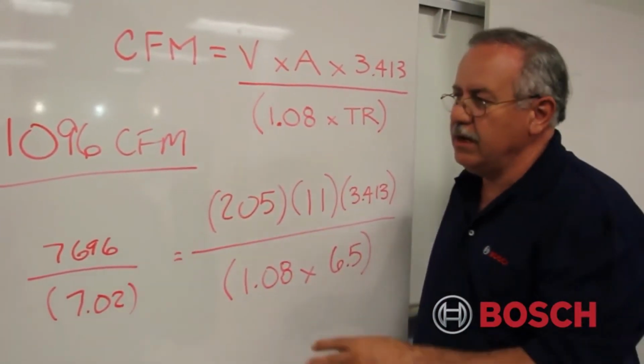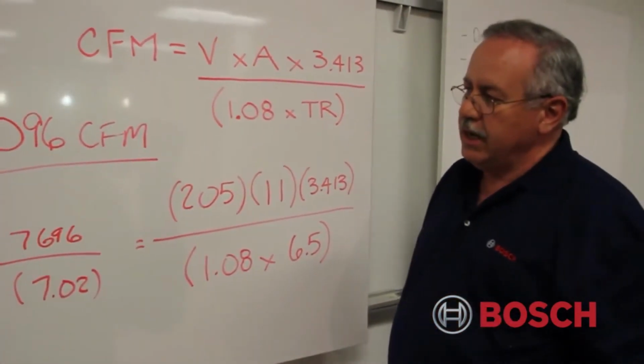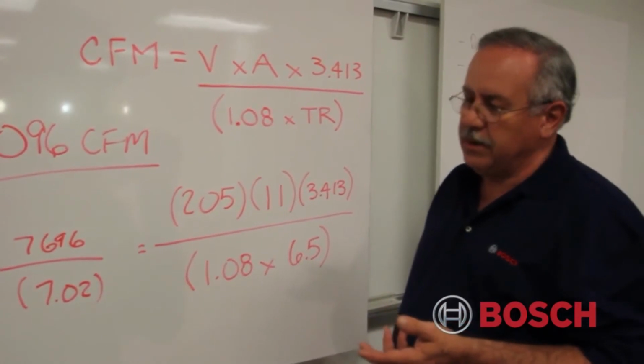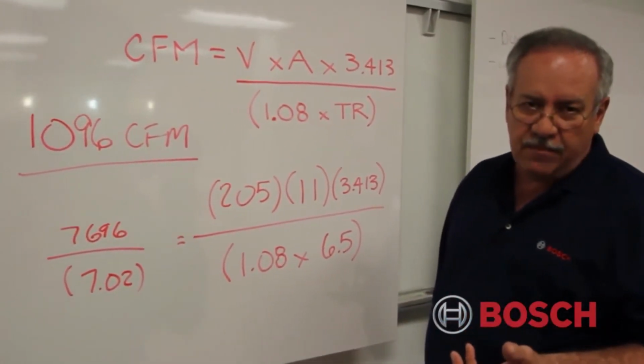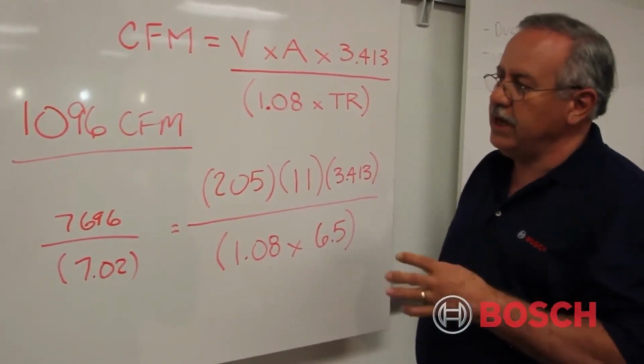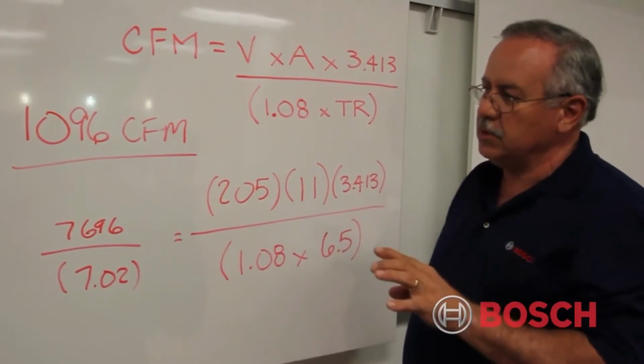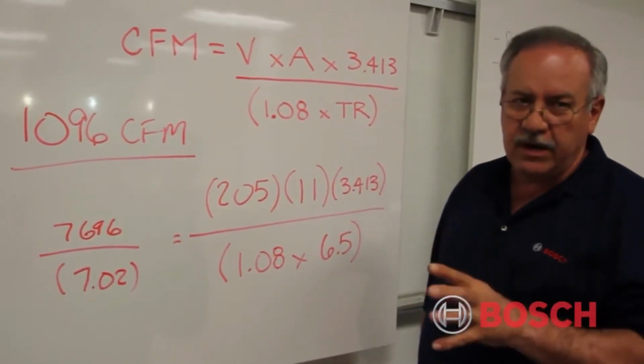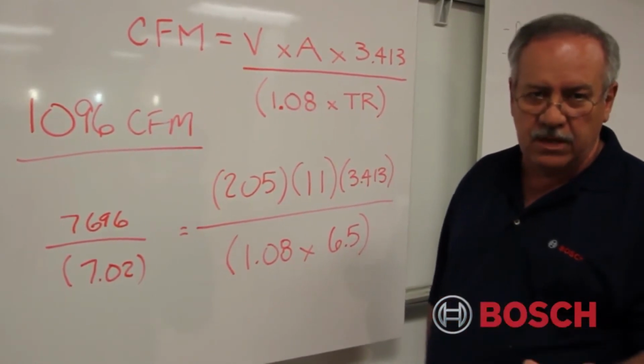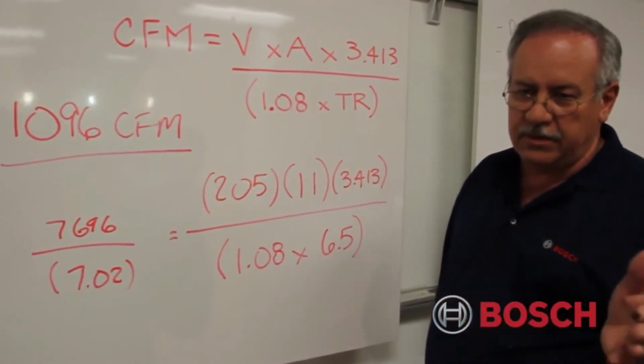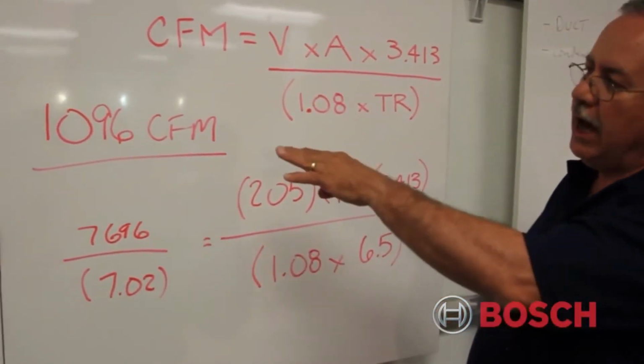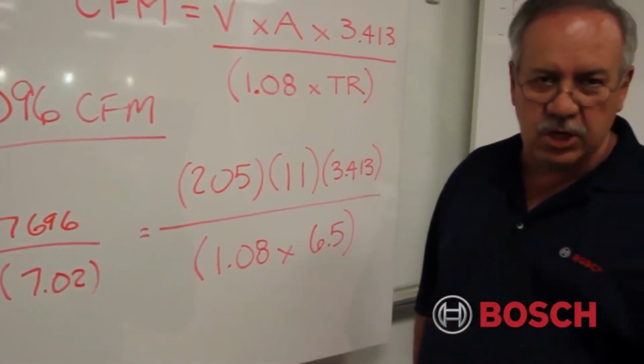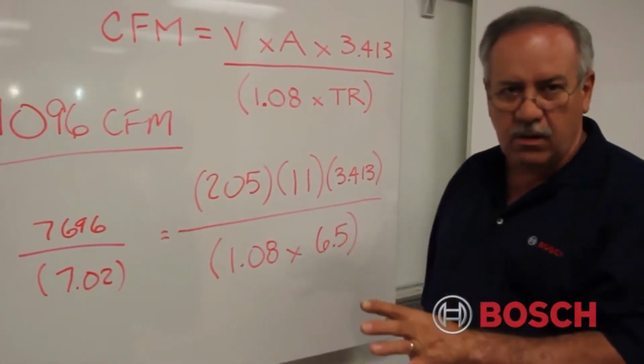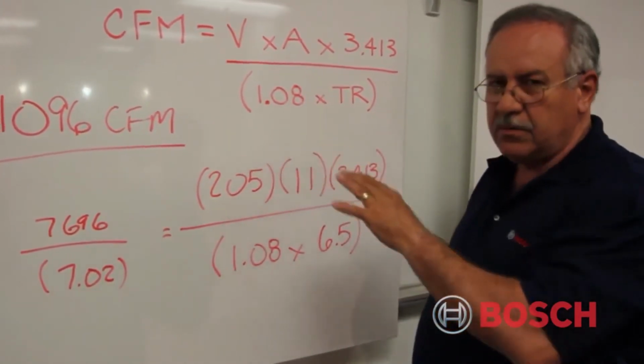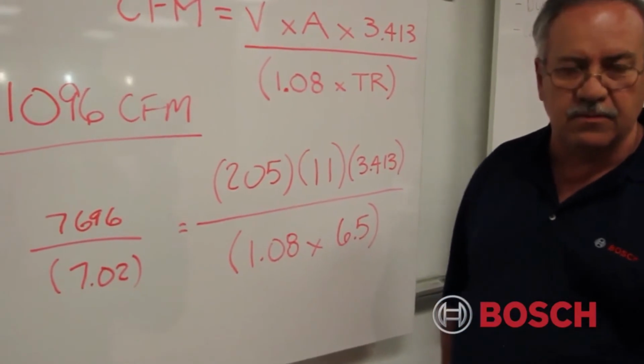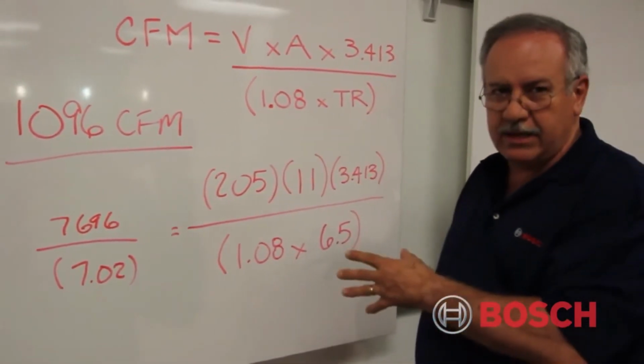Now in this particular case, I know that this machine is rated at 0.6 of an inch in its spec data, and it should be delivering approximately 950 CFM. Now if it is set on plus 15%, we could probably get this. Another situation, because we have very limited ductwork, we have very limited pressure or resistance against the airflow. So even though this blower operates against static pressure from 0 to over an inch of static pressure, I know that I'm developing at least what I think I should develop. In the field, where I have more ductwork in any particular application, the CFM would probably pull closer to what I expect it to be in the spec data. So this is the acceptable method to calculate CFM.